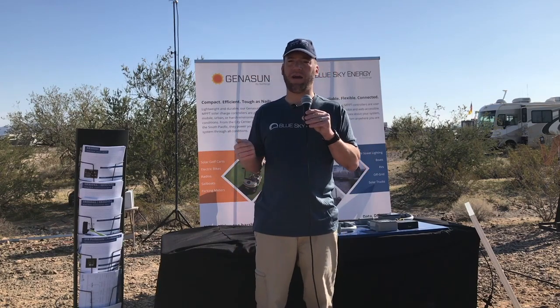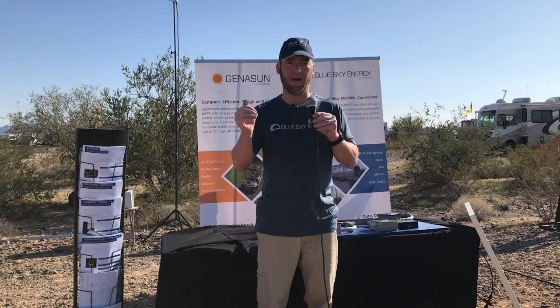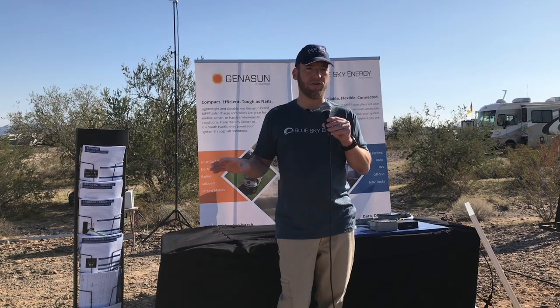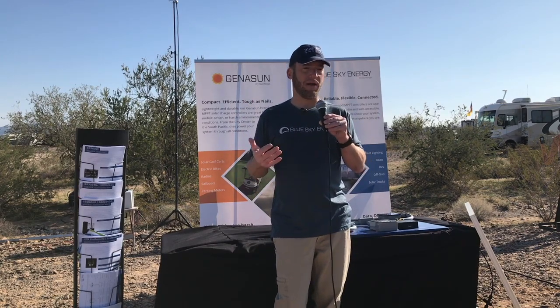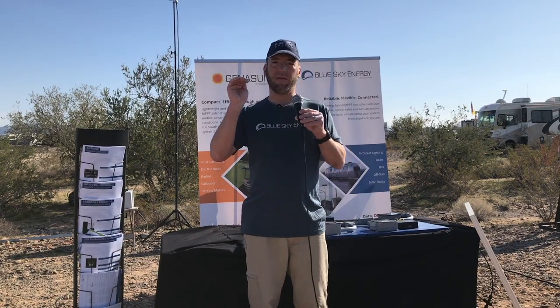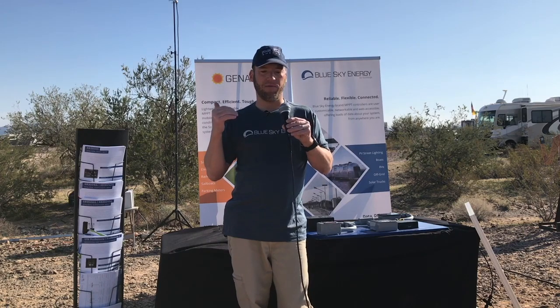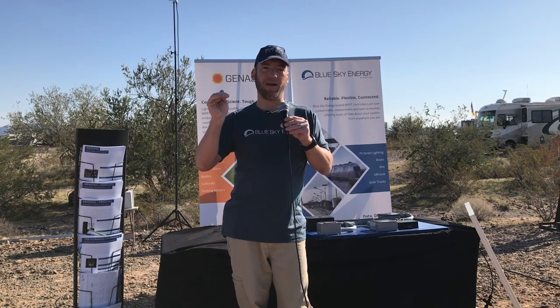That's because traditionally you don't float a lithium battery. You don't want to provide current to keep its voltage maintained. So the resting voltage of a fully charged lithium battery initially will be like 13.6 volts, maybe a little higher, and that'll settle down a little over 13.4 volts after a couple weeks. So if you choose a set point beneath that voltage, then you're not actually providing current to maintain it.